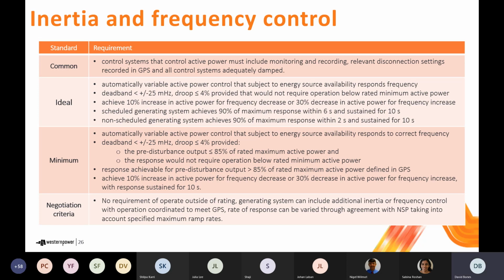So the main aspect of the common requirements are to install appropriate monitoring and recording equipment to be able to demonstrate that you're meeting the requirements of your performance standard after an event. And importantly, that the GPS must record any relevant disconnect settings or protection settings, and that all controls providing the frequency response are adequately damped.